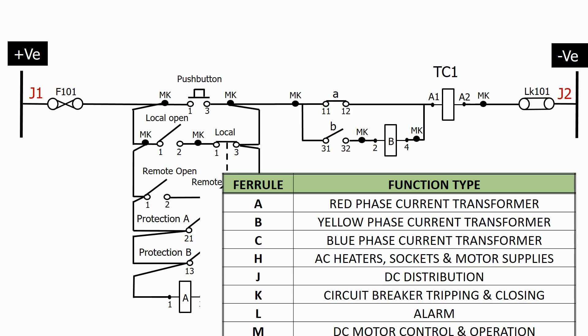What about the main circuit itself? As we've said, this is a circuit breaker trip circuit, so therefore we need to use the K prefix. As before, all the positive signals are odd numbers, so let's use K1, K3, K5, K7, K9, and finally K11.